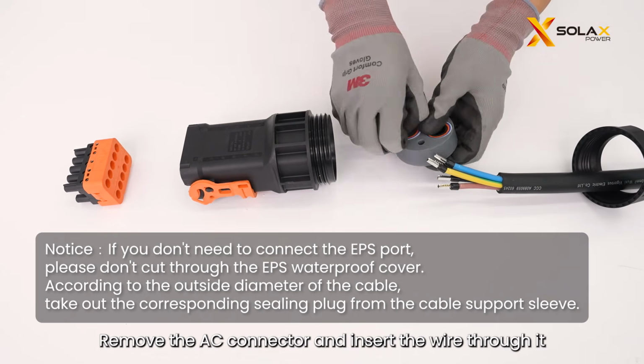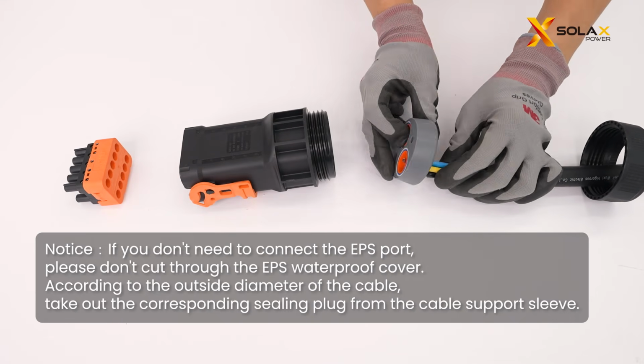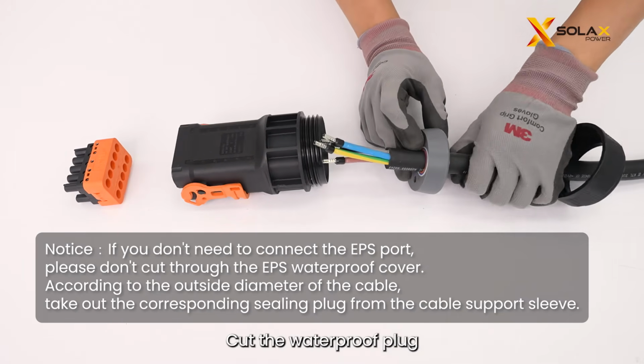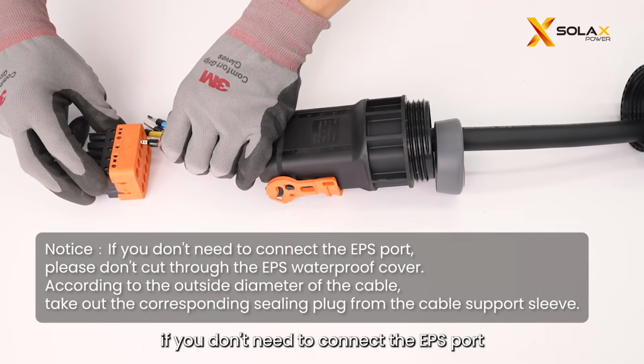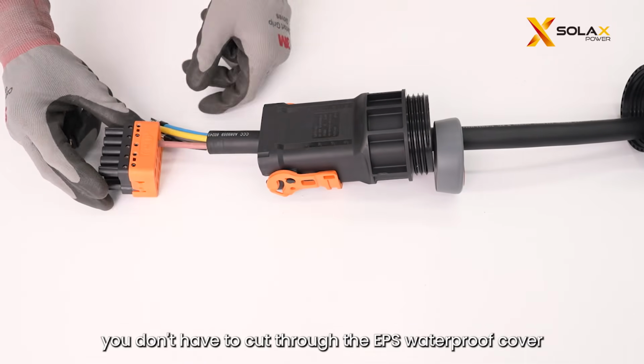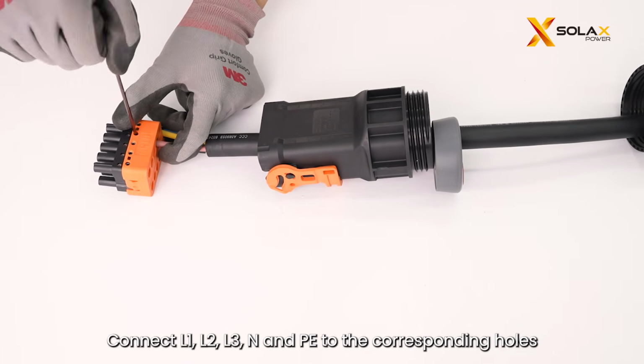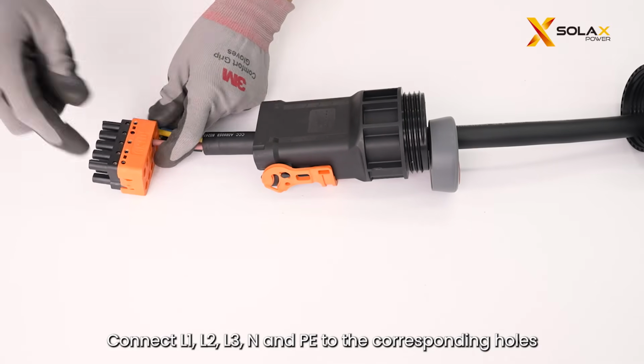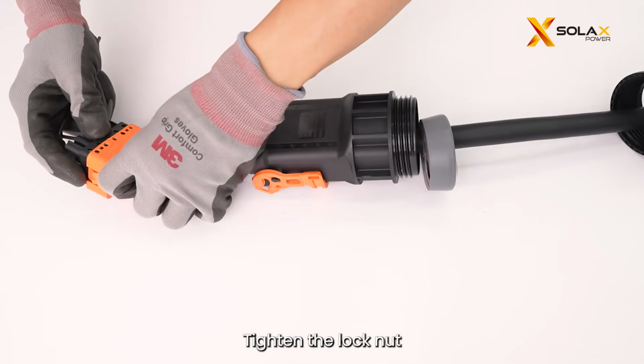Remove the AC connector and insert the wire through it. Cut the waterproof plug. If you don't need to connect the EPS port, you don't have to cut through the EPS waterproof cover. Connect L1, L2, L3, N and PE to the corresponding holes, tighten the lock nut.